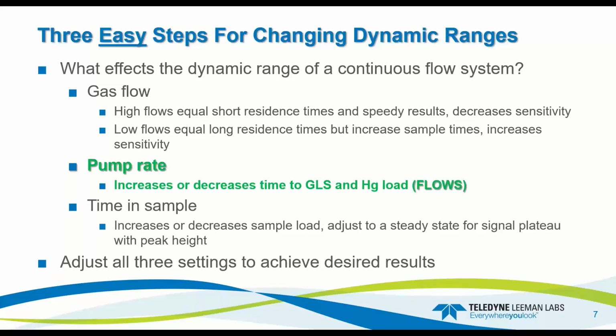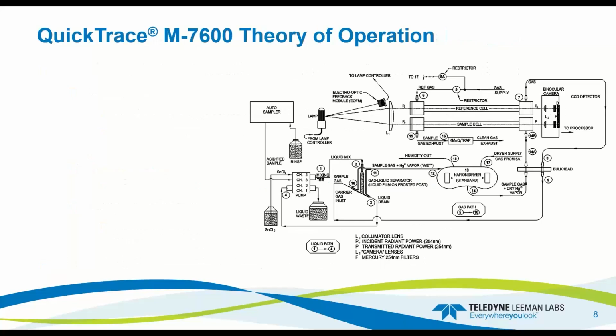So if you increase the sensitivity, you can drive the system down to a lower method detection limit and or instrument detection limit. Pump rate, same thing. That's going to increase or decrease the time to the GLS, the Hg loads into the system. And then time in sample is basically the same. So it'll increase or decrease the sample load and adjust to a steady state. If you're doing peak height and you want to look at the signal plateau, you want it somewhat flat. If you're doing peak area, you can run the system relatively fast and you just measure everything under the peak itself. So you adjust all 3 settings to achieve the desired results.